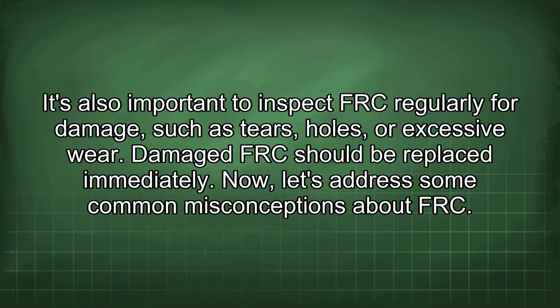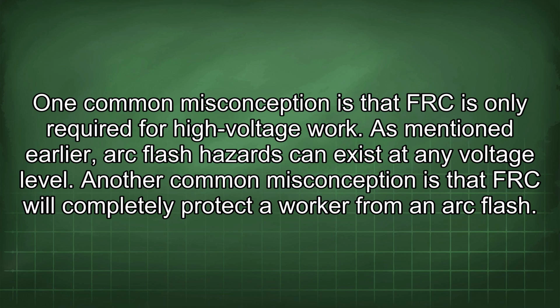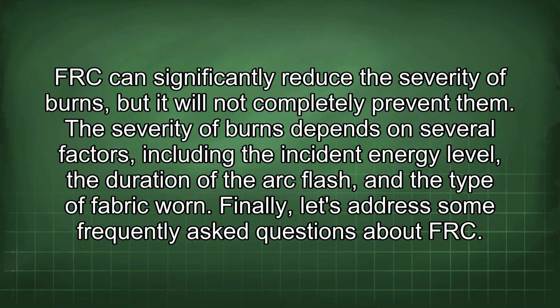Now, let's address some common misconceptions about FRC. One common misconception is that FRC is only required for high voltage work. As mentioned earlier, arc flash hazards can exist at any voltage level. Another common misconception is that FRC will completely protect a worker from an arc flash. FRC can significantly reduce the severity of burns, but it will not completely prevent them. The severity of burns depends on several factors, including the incident energy level, the duration of the arc flash, and the type of fabric worn.